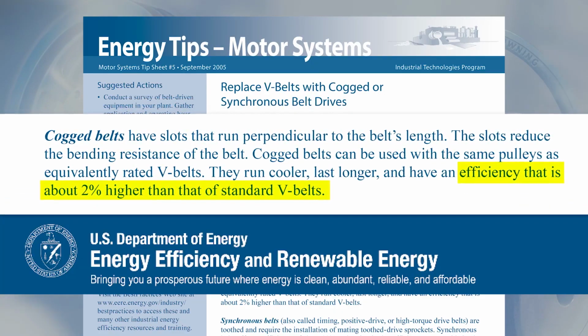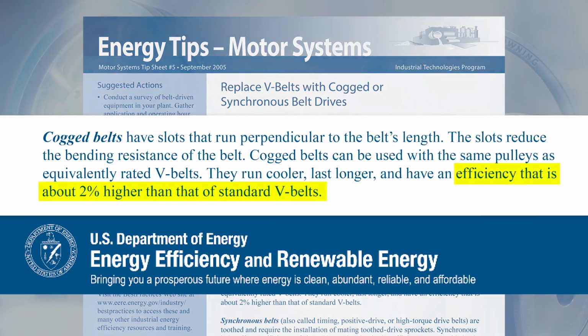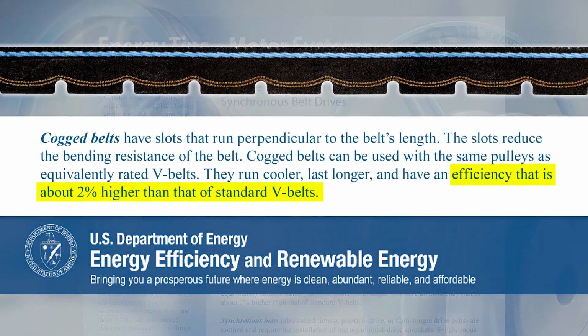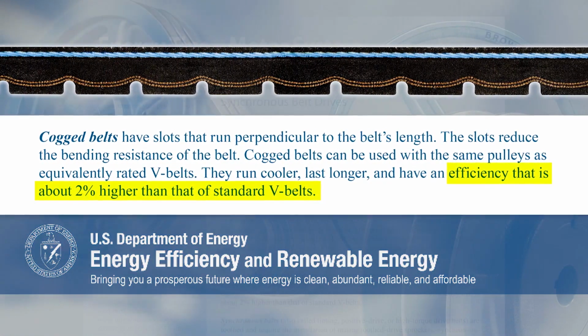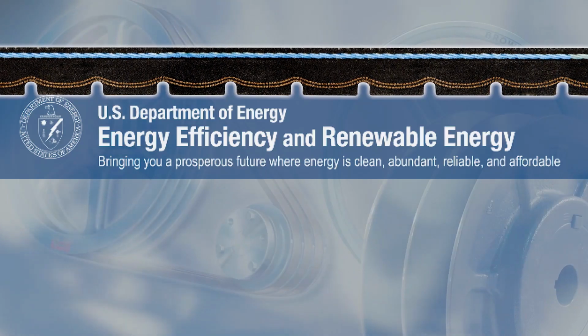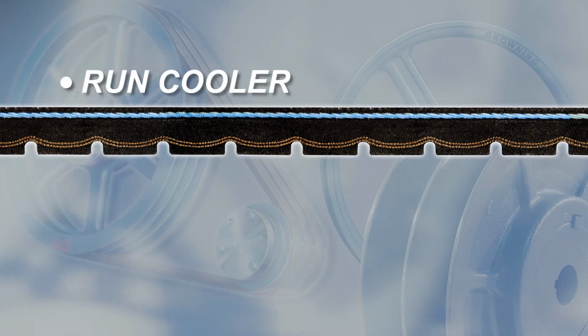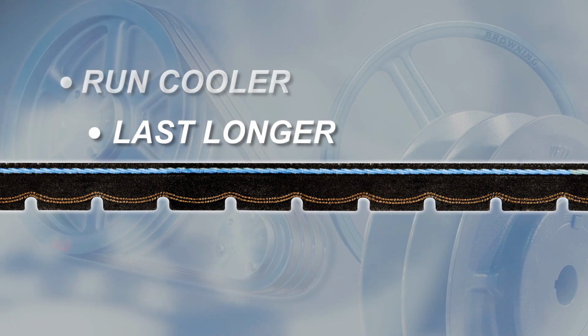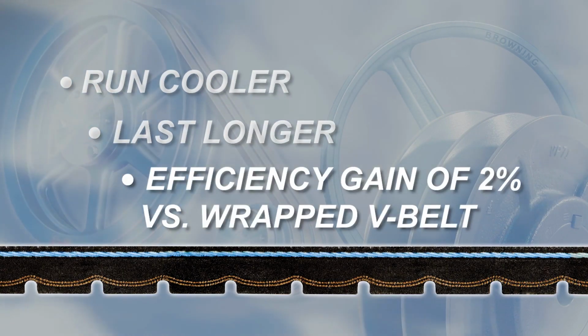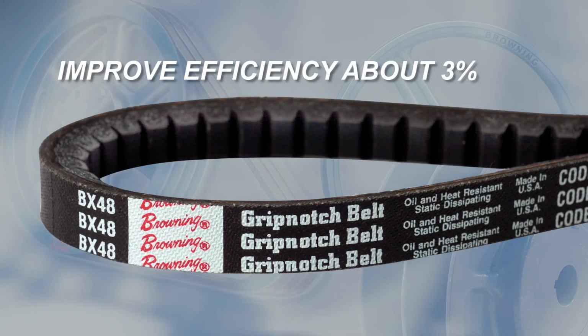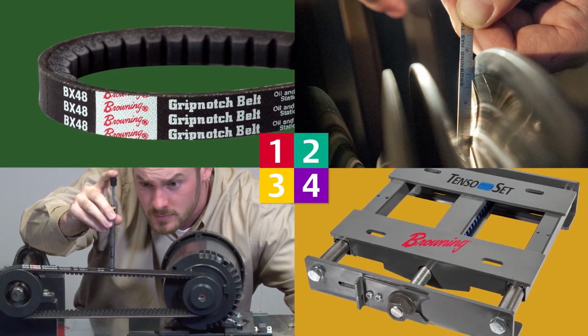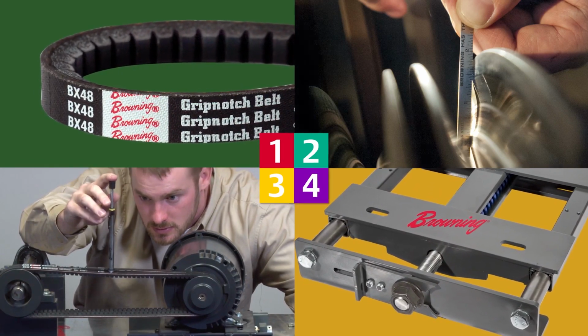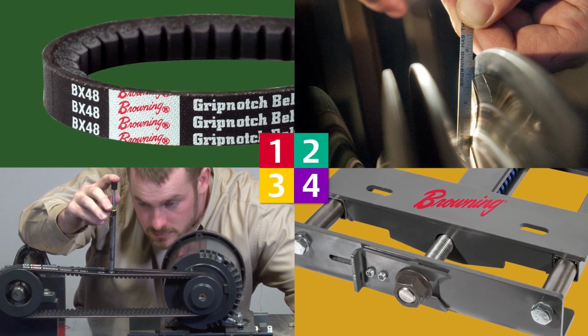The U.S. Department of Energy publishes that notched V-belts, often called cog V-belts, are more energy efficient than standard wrapped V-belts. They also publish that they run cooler, they last longer, and they have an efficiency that is about 2% higher than that of a standard wrapped V-belt. Independent tests have shown an efficiency gain of about 3%. Energy responsibility with belt-driven fan applications can be managed in 4 easy steps.